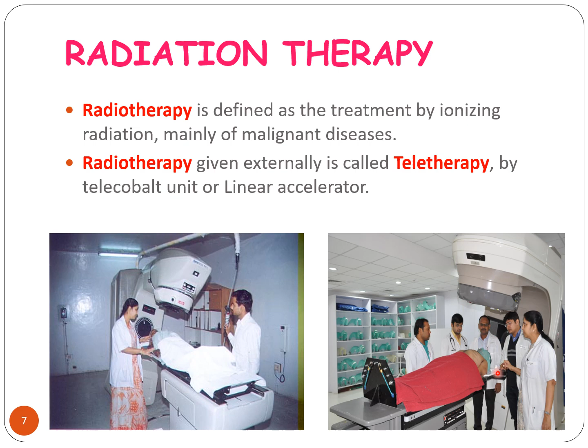In a teletherapy unit, the treatment is delivered from a distance. These units are the telecobalt unit, where the radiation source is cobalt 60, and the linear accelerator, where radiation is produced by electron bombardment of a tungsten plate and photons are generated. Here this is the telecobalt unit. The patient is lying down on the couch and the treatment field is set up. Here this is the linear accelerator unit. Again the patient is on the couch and the fields are set up.